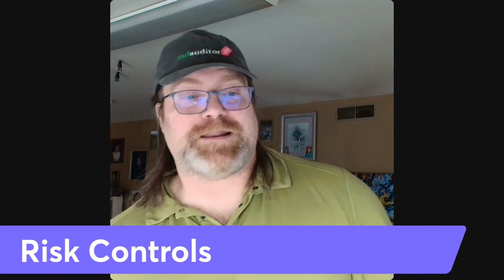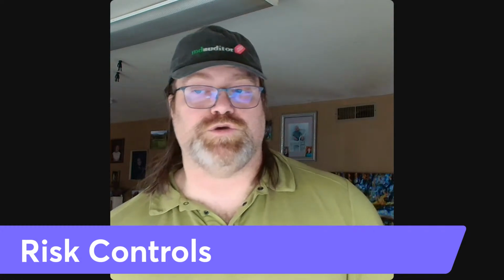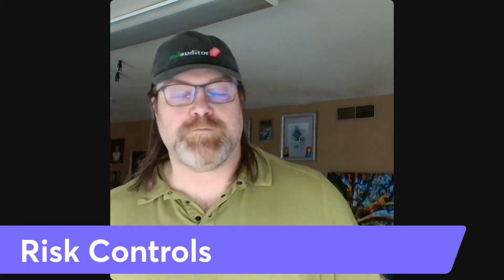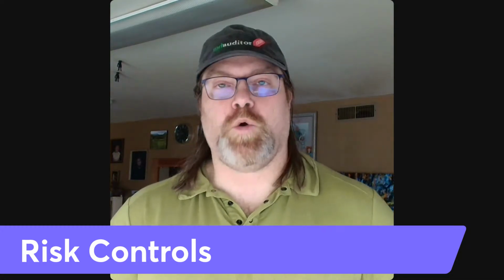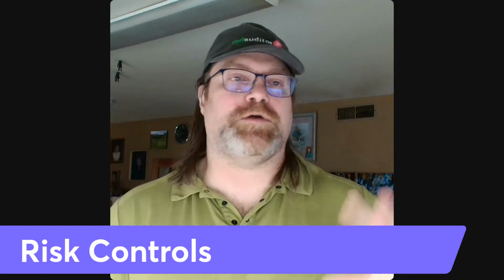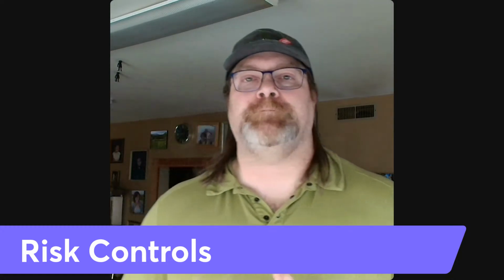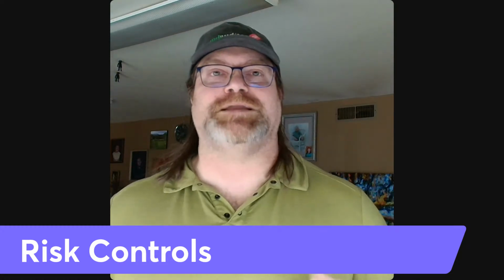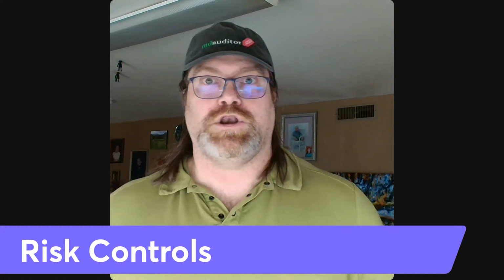Now we're going to talk about a couple of risk controls that you can use in general for either method to improve things a lot. So number one, proactive planning. A lot of the clients, whether they're using Agile or they're using Waterfall, what I hear is, I'm not ready to create a design plan or start a design history file because my design isn't done. No, that's not how it works. It's a plan. It says right in the regulations.